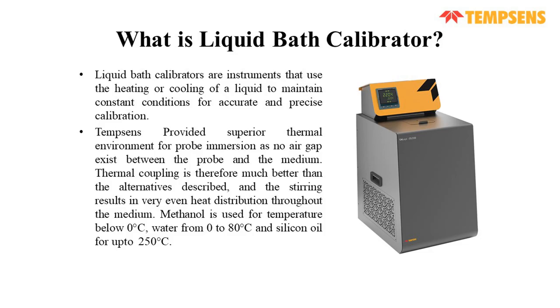Then we are moving to the liquid bath calibrators. Liquid bath calibrators are instruments in which the liquid is heated or cooled and maintained at a constant condition for accurate and precise calibration. In this, there is no air gap between the probes, so it has high uniformity. Thermal coupling is therefore much better than the alternative described, and the stirring results in very even heat distribution throughout the medium. We have three types of liquid that we can use in these models: methanol when temperature is below 0°, water from 0 to 80, and silicon oil up to 250°.